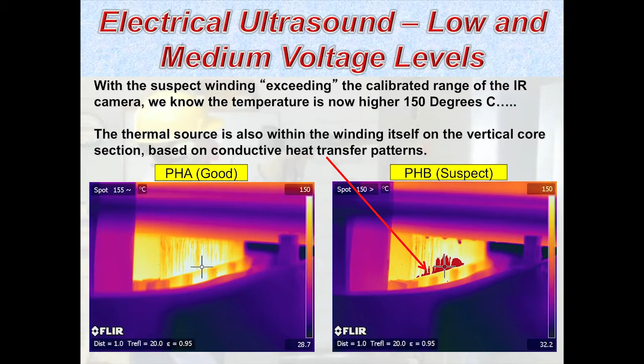But this one here was certainly higher. It exceeded the dynamic range of the camera. And the other thing that was suspect to me, even though the range was exceeded from a temperature measurement standpoint, I don't even think about temperature at first. I'm looking at patterns. Rick will tell you that. Right? I talk thermal patterns when it comes to electrical because it allows me to identify the origin of the thermal energy and the direction of flow. And that's important when you're trying to find the cause of these symptoms.